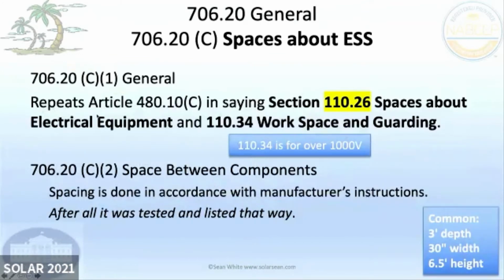Other things with energy storage systems, we just have to follow the regular parts of the National Electrical Code. There are different rules about working spaces around equipment, and 110.26 is oftentimes used. This is for PV equipment, energy storage equipment, and all different kinds of equipment. For most jobs where you put something on the wall, it's a 3-foot depth, so you have to be 36 inches away from it. So you don't put it in some narrow closet. It's 30 inches of width, or at least the width of the equipment, and 6.5 feet high, just like a regular basketball player. And that's just what a table looks like in the NEC.